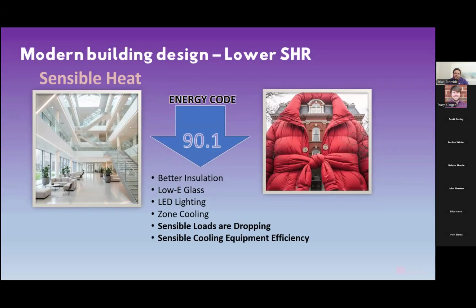So why are we even talking about this? Well, a couple of different things. Energy Code 90.1 is allowing us to start having less and less sensible heat in the building. So whether that's through better insulation, lower emissivity glass, LED lighting, zone cooling, the sensible loads are dropping. So air conditioning systems are not handling necessarily so much of the sensible load anymore, but also the sensible cooling equipment is becoming more efficient. But the way that we make the sensible equipment even more efficient is by taking the latent load off of it.